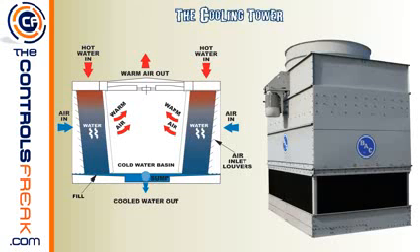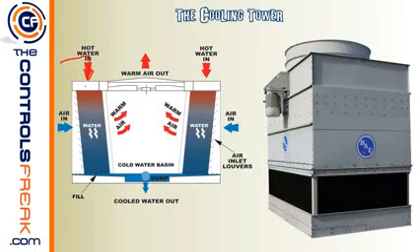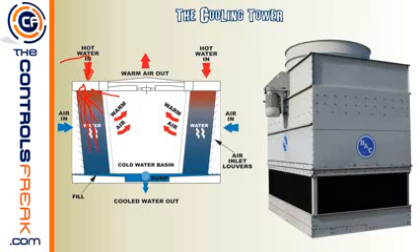The cooling tower's purpose relates to the condenser side of the centrifugal chiller — it has hot water coming out that needs to be cooled down to keep the chiller operating properly. In the diagram, hot water comes into the cooling tower and either drips down the side of the tower or is sprayed through spray heads to disperse it across the tower, raining down across the fins.